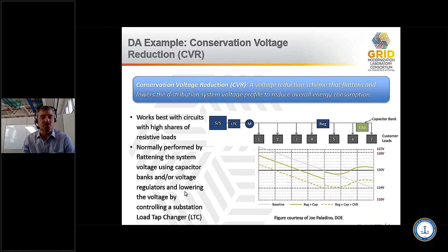This is centered around 120 volts, the standard service voltage we expect. Some people are a little higher, some a little lower, that's normal. But with conservation voltage reduction, you're trying to get that dotted line, controlling your equipment to get the voltage as low as you can while staying within the proper range, nothing lower than 114 volts on a 120 volt base. That's the basic idea behind conservation voltage reduction.